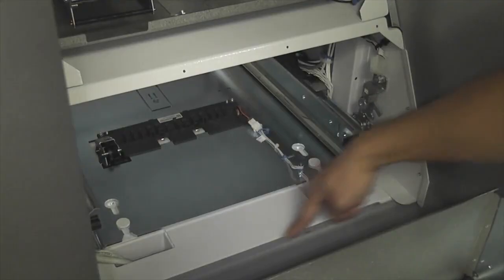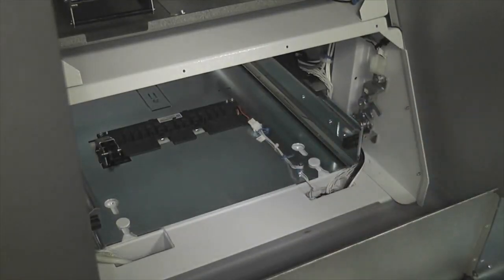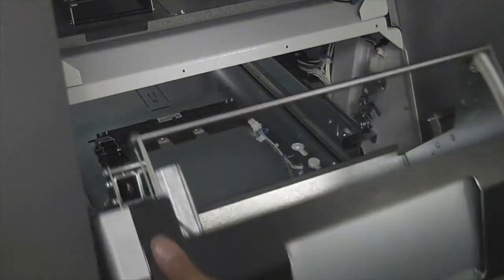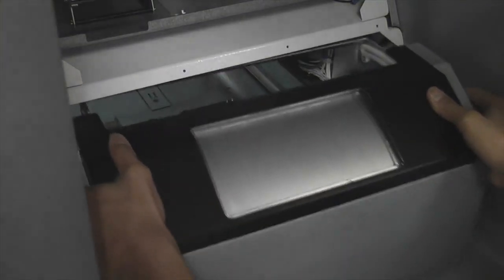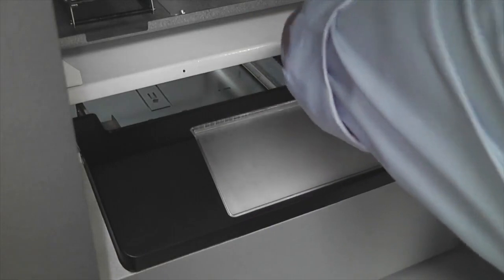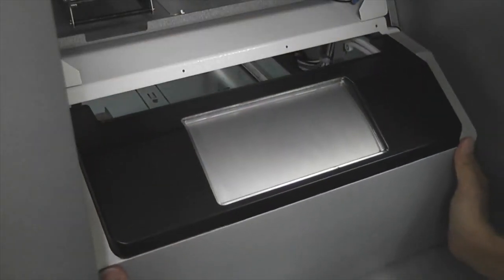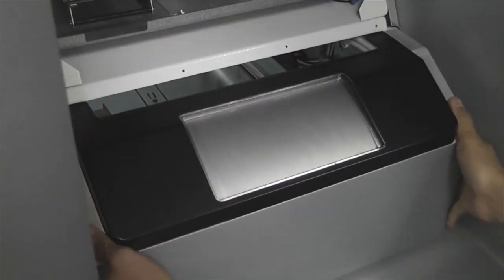When replacing the shutter assembly, ensure that it is properly positioned on the frame. Slide it into the machine and connect the white signal and power connector. Push the assembly firmly into the machine to properly engage the latches.